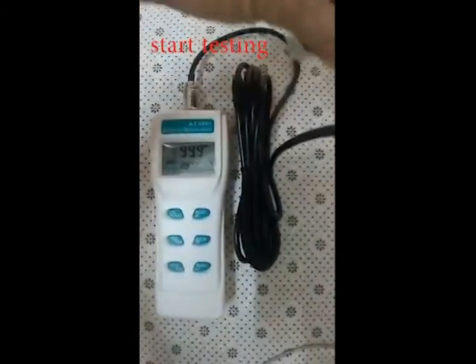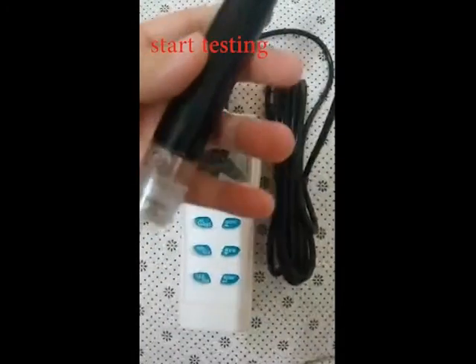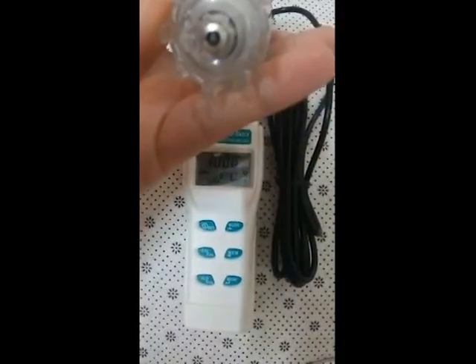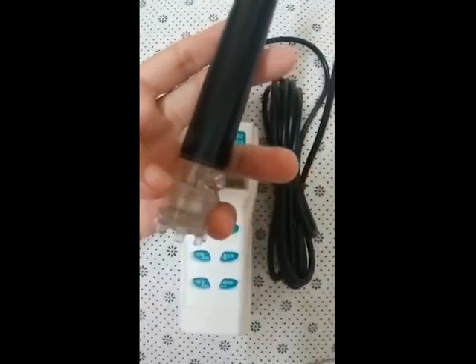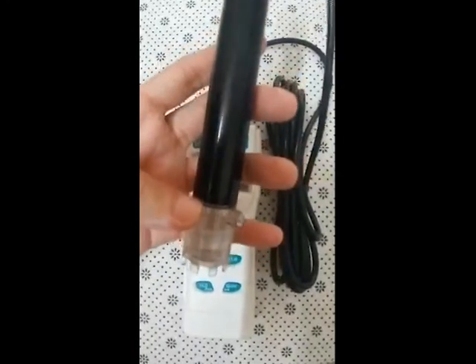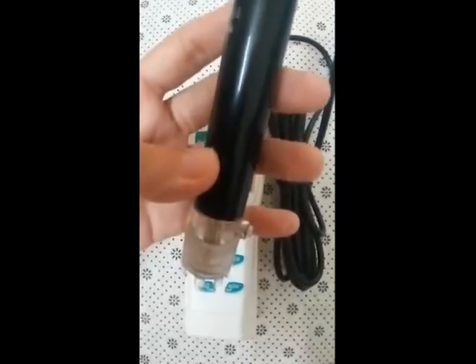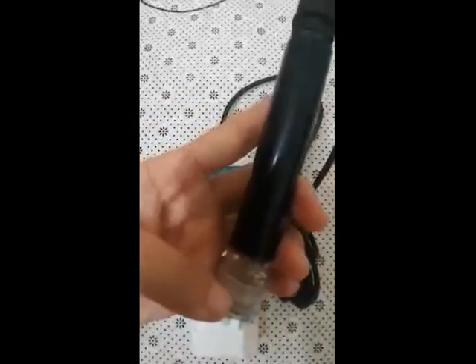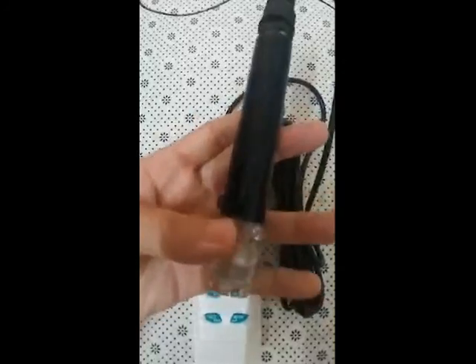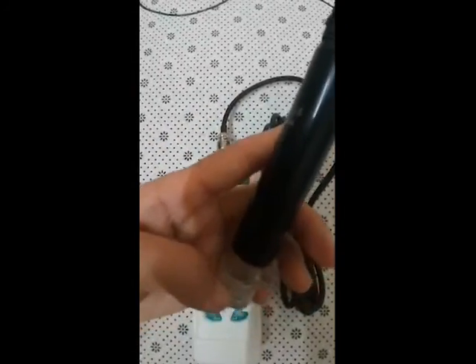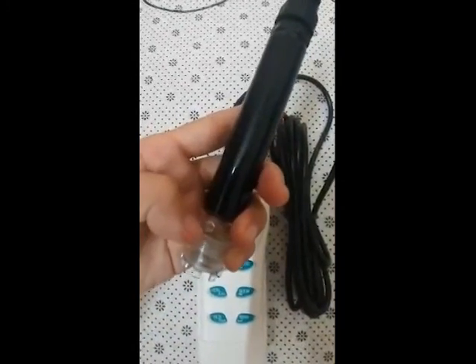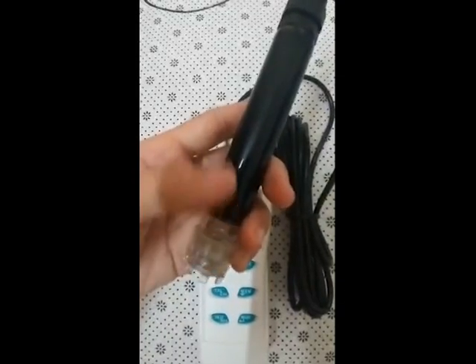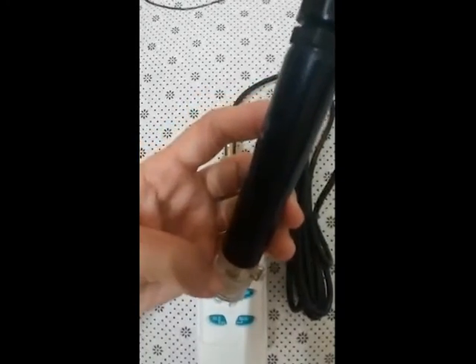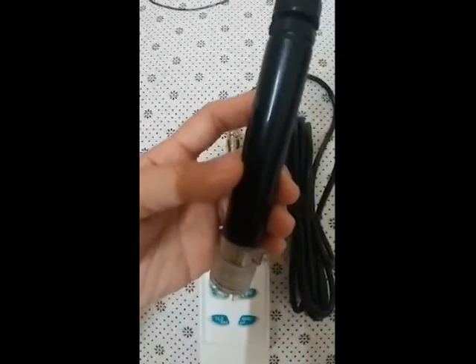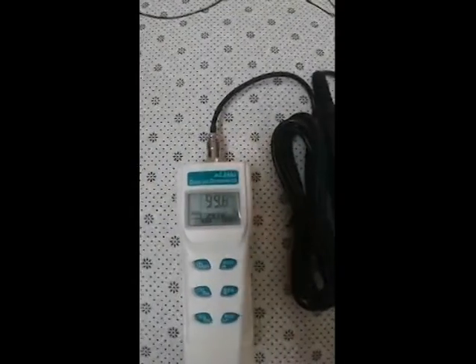When you start to test using this one, you check the membrane. Make sure the membrane is in good condition. If it's not in good condition, you can replace it. Follow the manual. Then you check the electrolyte solution level. Make sure the solution is enough to cover all the electrode. If not enough, you can turn the screw and refill the electrolyte solution with the provided syringe. After everything is ready, you can start to test your solution.